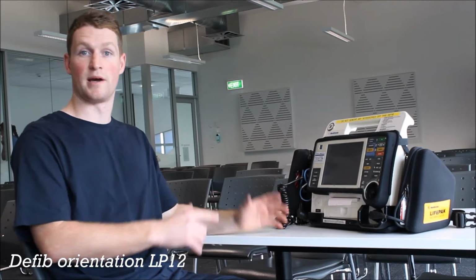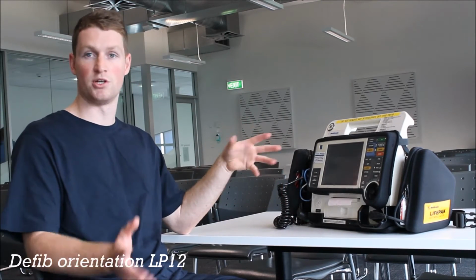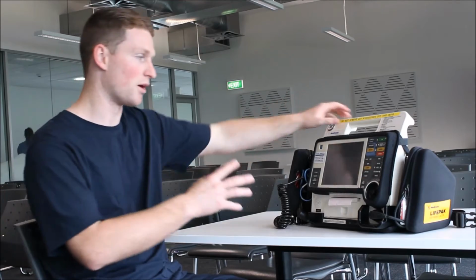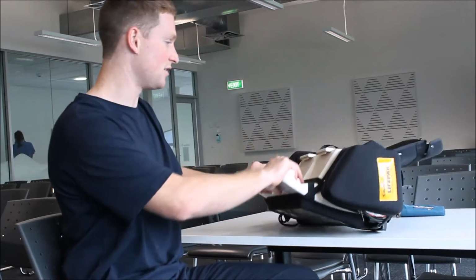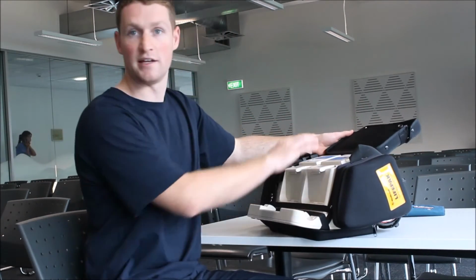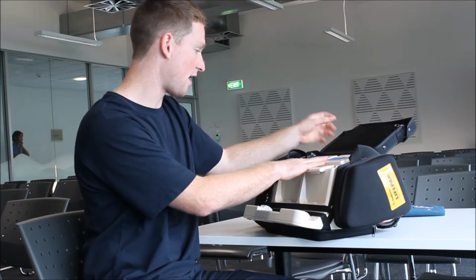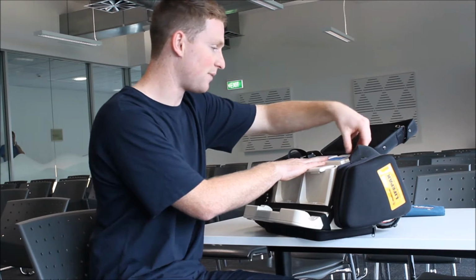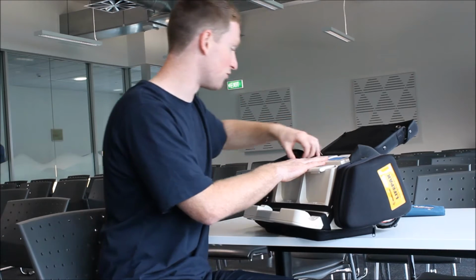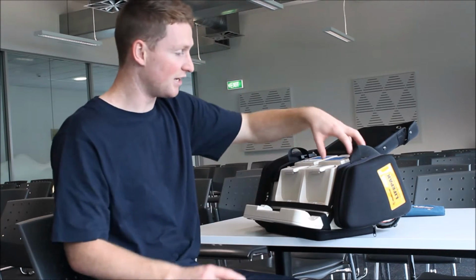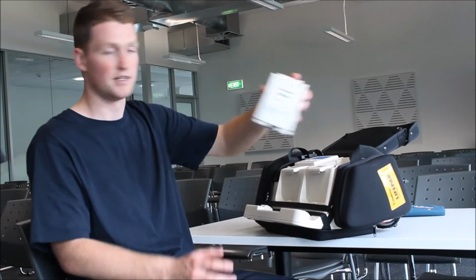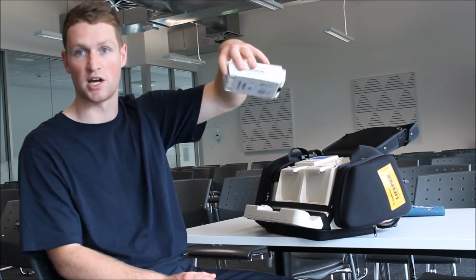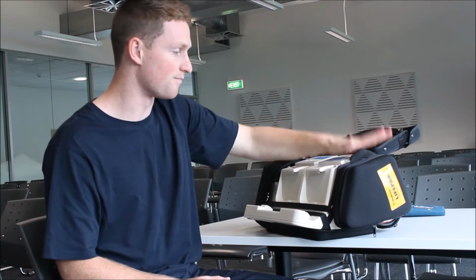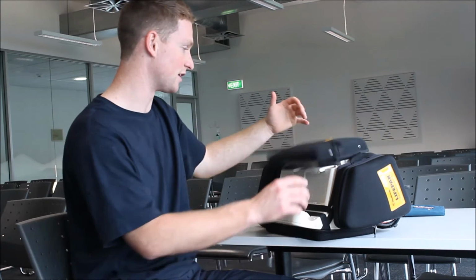Next up, I'm going to be talking about the LIFEPAK 12. So first thing we should do is check the batteries and that everything's in the pockets. To check the batteries, roll it over, and in the back are the batteries. You can push the little black button on top of them and they both show full batteries. If you want to take them out, you can push the button on the side, then put them on charge and back in the machine when they're fully charged. So that's how you check the batteries.